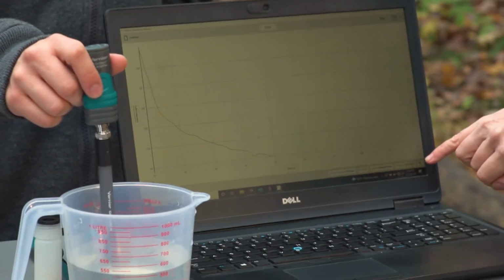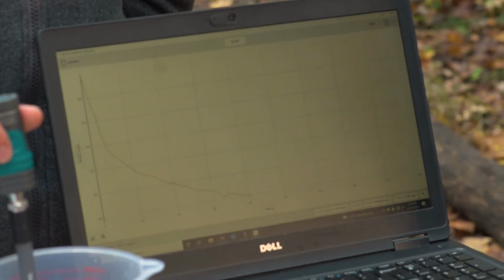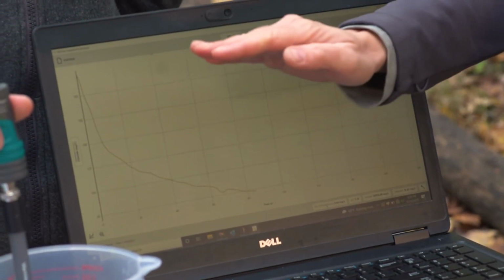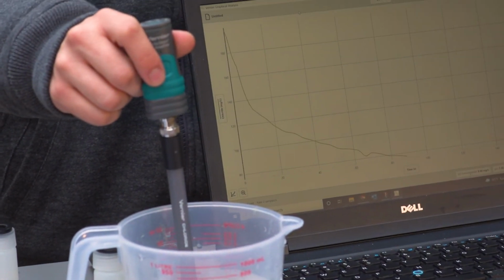I'm looking here, we're stabilizing a little bit - we're kind of in the 79-80 milligram per liter range on our sample of the chloride reading. So our little red checker wouldn't have been enough for this sample. You can go ahead and stop that one.